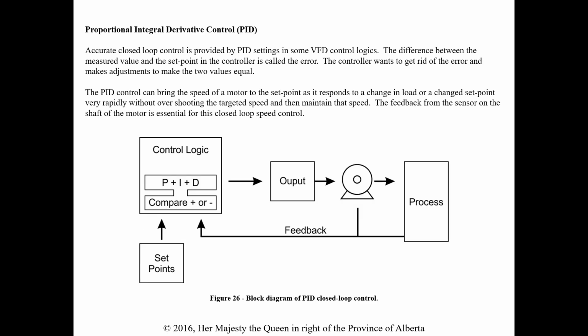Proportional integral derivative control, so PIDs. I've done some instrument and some skids, so we definitely saw a lot of PIDs, not knowing exactly what they were at the time, just hooking them up. Accurate closed loop control is provided by PID settings in some VFD control logic. The difference between the measured value and the set point in the controller is called the error. The controller wants to get rid of the error and makes adjustments to make the two values equal. So that's how it's taking that feedback and adjusting to that set point.